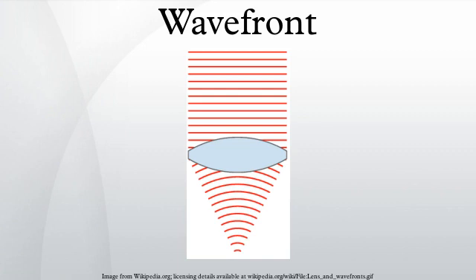Mathematical techniques like phase imaging or curvature sensing are also capable of providing wavefront estimations. These algorithms compute wavefront images from conventional bright field images at different focal planes without the need for specialized wavefront optics. While Shack-Hartmann lenslet arrays are limited in lateral resolution to the size of the lenslet array, techniques such as these are only limited by the resolution of digital images used to compute the wavefront measurements.